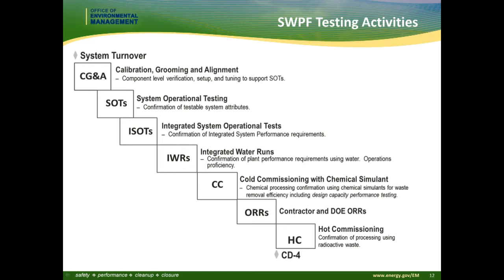Then we go into cold commissioning mode, running the plant full up. By that phase of the project, when we get to integrated water runs and cold commissioning, we should have knocked out all the problems in the operation of the equipment, the mechanical aspects of the facility, and a lot of the procedural elements. So now we're into proficiency - maturing our workforce, maturing our procedures, making sure we're ready to operate in a normal mode. When that phase is finished, we go into the operational readiness reviews and then hot commissioning.